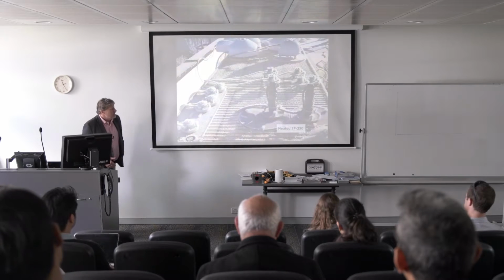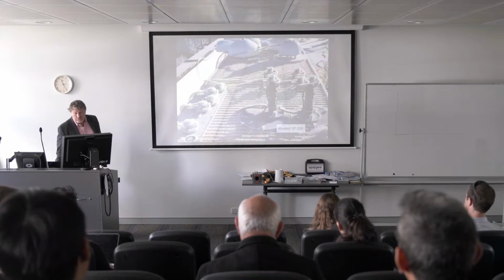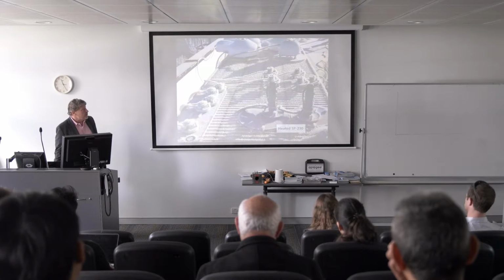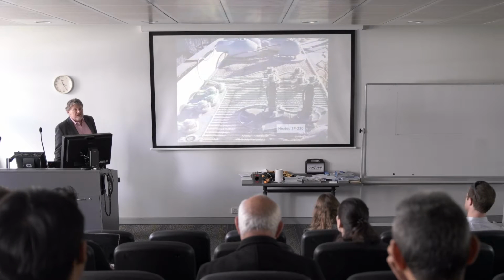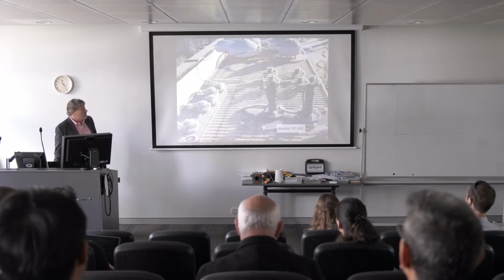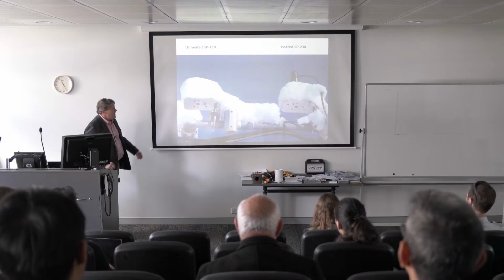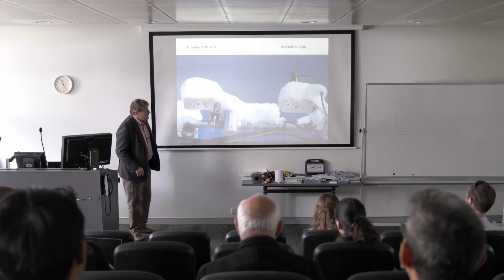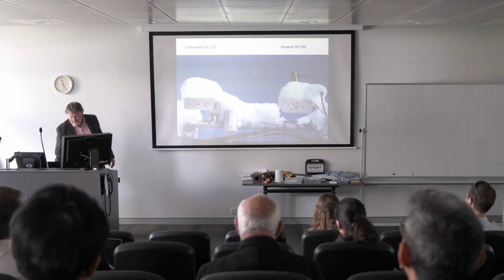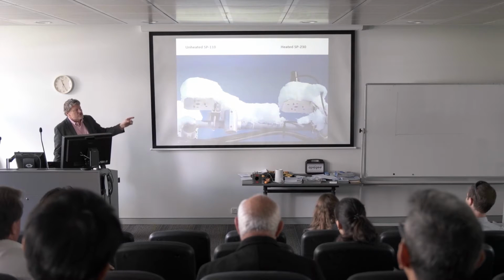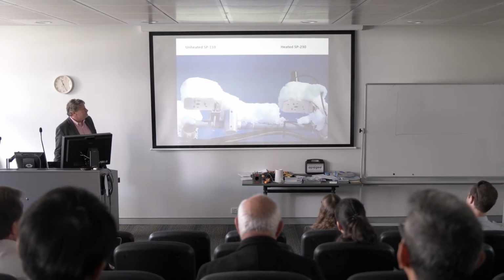So those heaters have helped quite a bit to help people make more accurate measurements in places that get condensation or in places that get snow and frost. Here's some example of snow, buried under snow here and above the snow there. It's also on a pedestal to keep it above so snow can't stick to it.